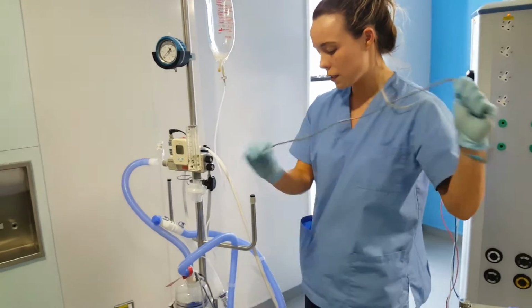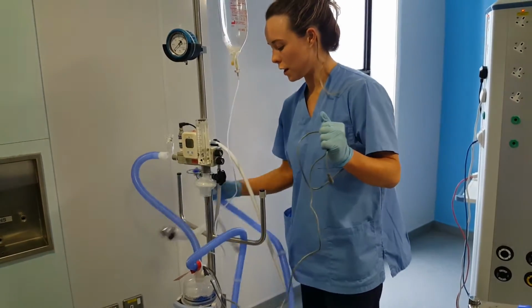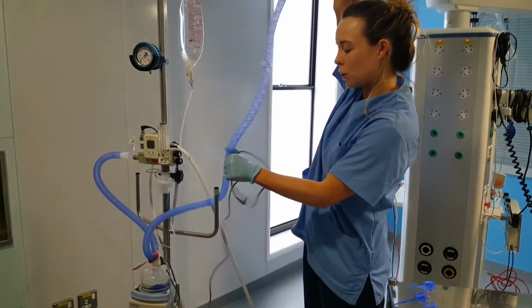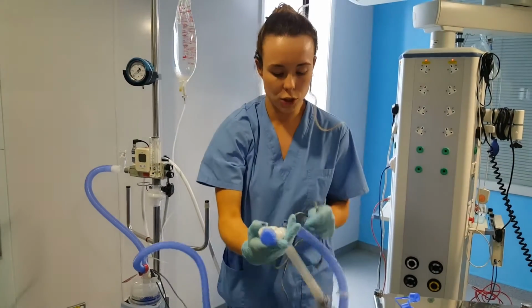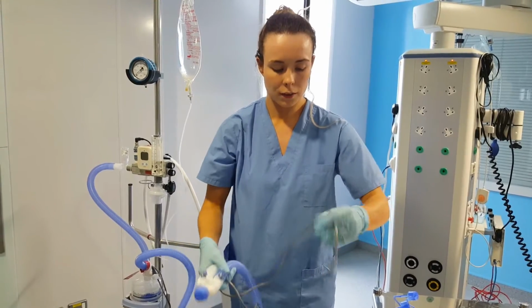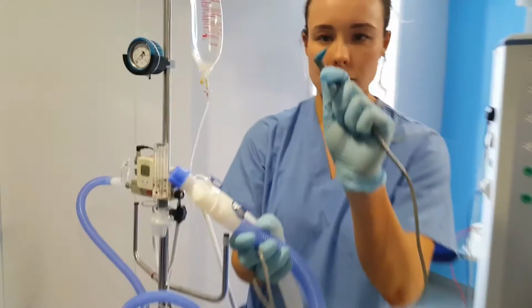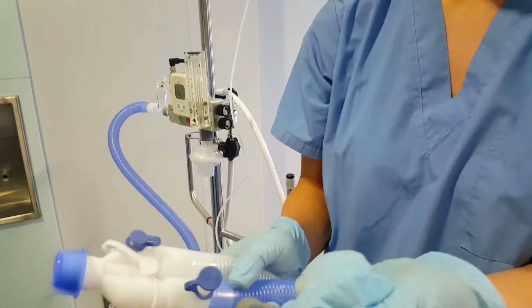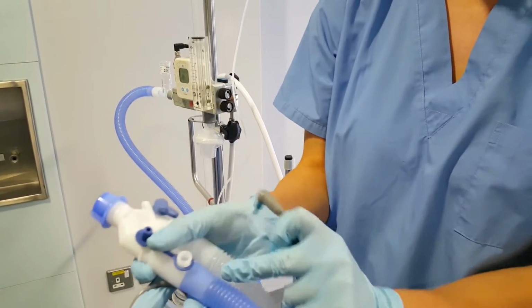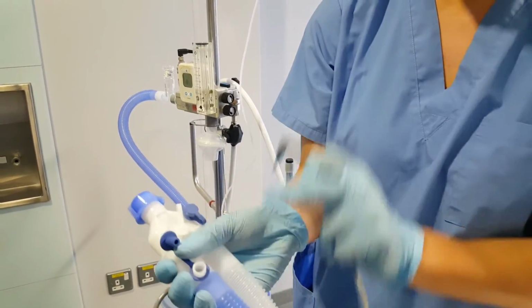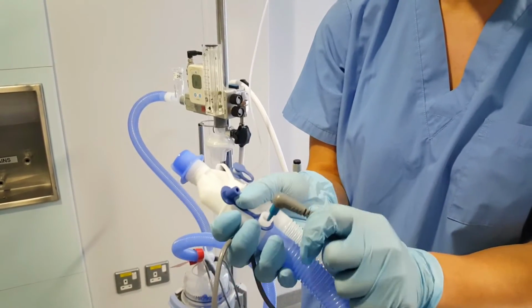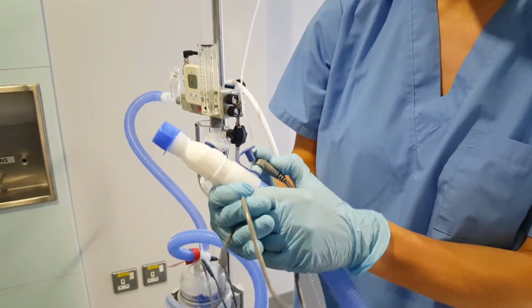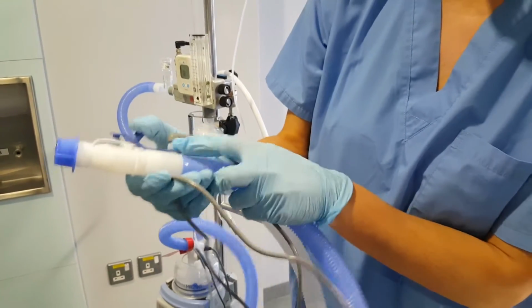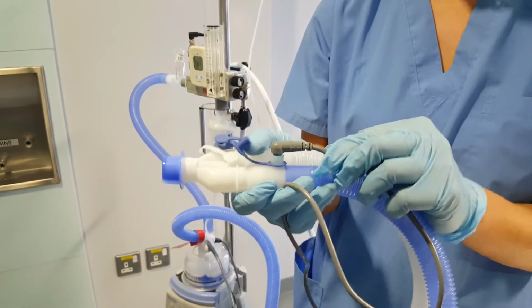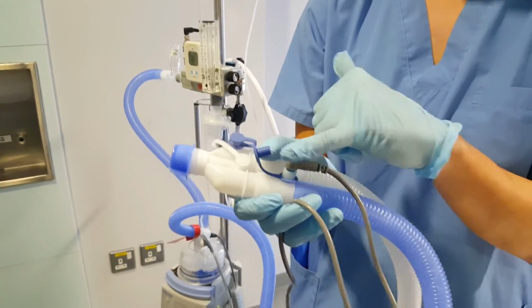You then just feed your heating wires up to the top of your long tubing, which is going to be connecting to your patient. And you pop the end temperature monitoring probe into this port on your blue tubing, not here on your grey or white, here on your blue. And you just click it in like so. You need to make sure that this is quite secure, and be aware that if your humidifier does alarm, it may be because this area, this probe may be wet. Just be conscious of that.